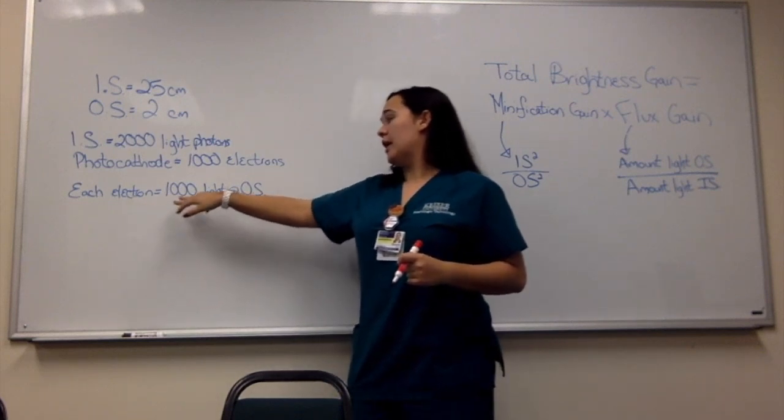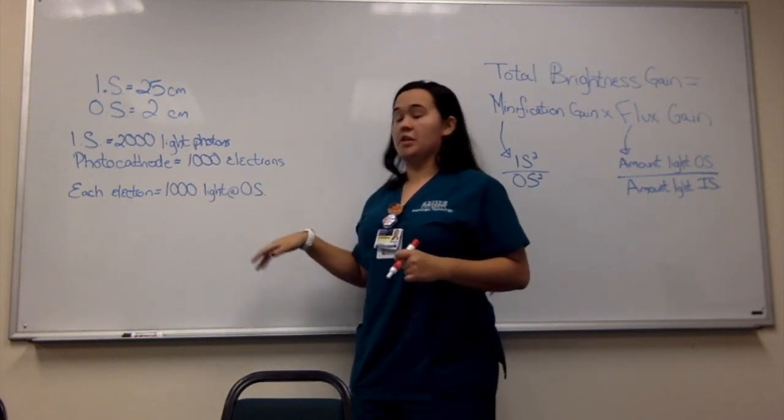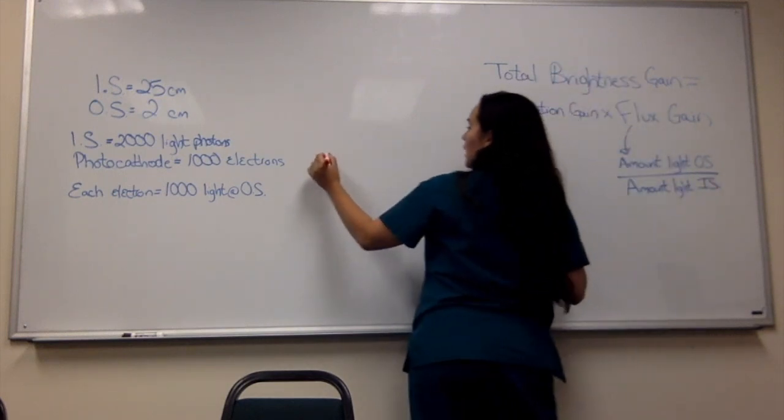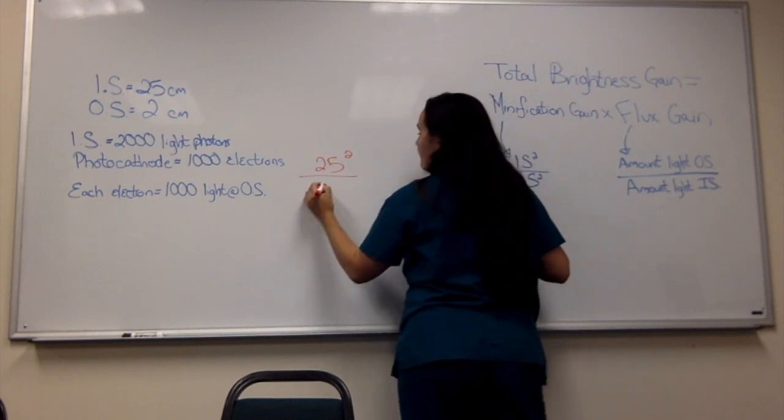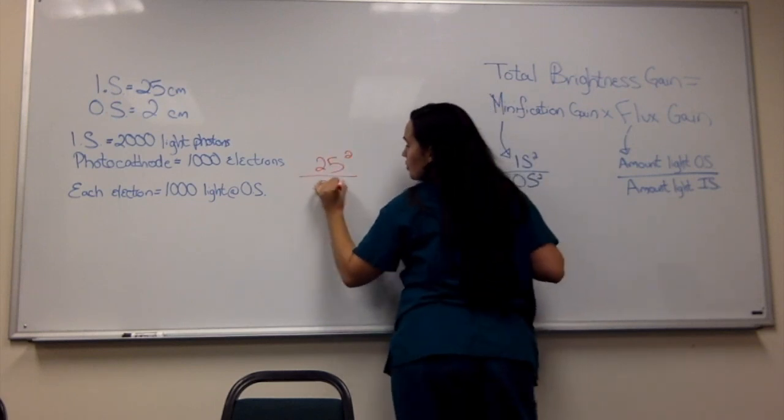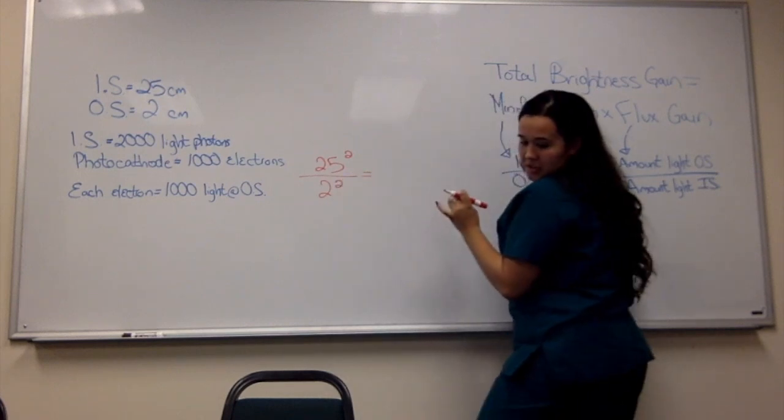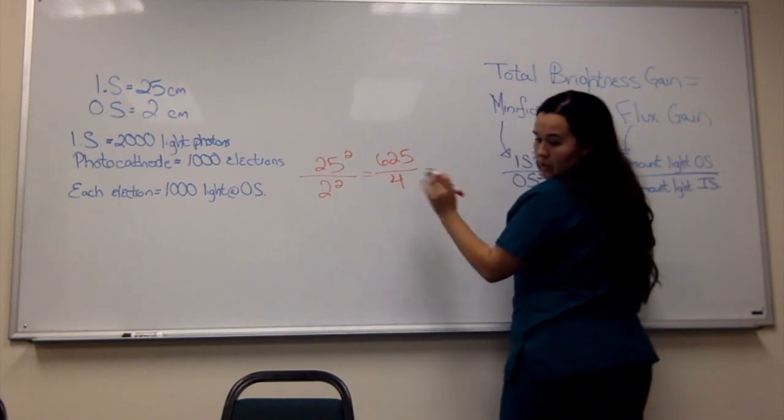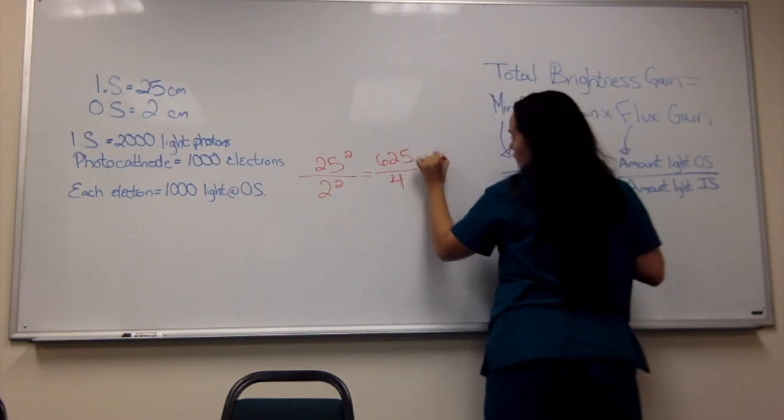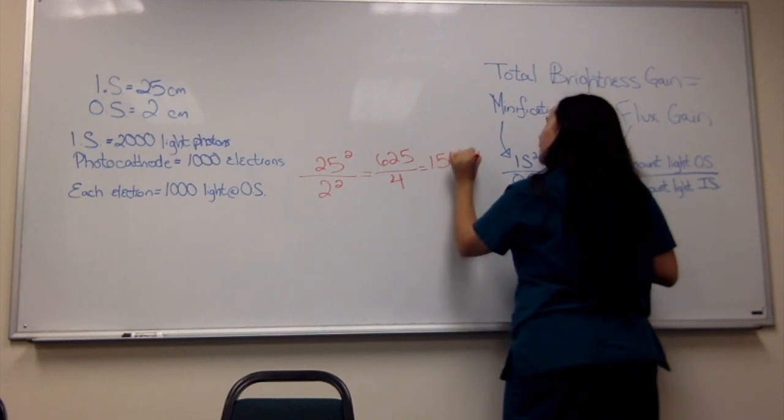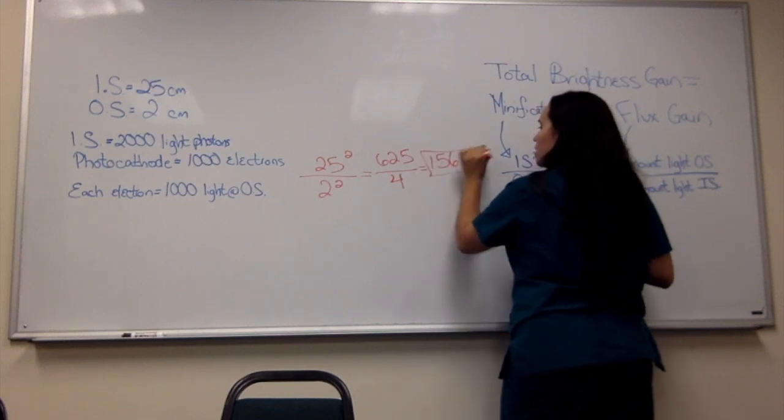So in order to find the minification gain, I'm going to take the input screen size, which is 25 squared, divided by 2 squared. So this is going to give me 625 divided by 4. When I do the math, it's going to give me 156.25. So this is the minification gain.